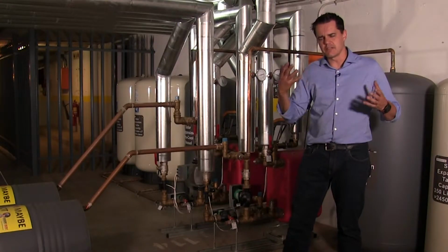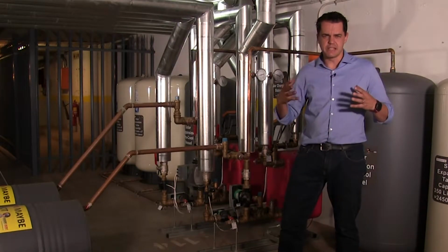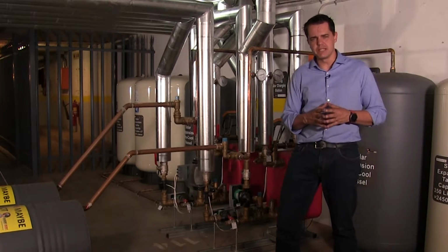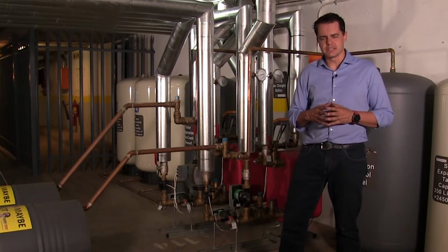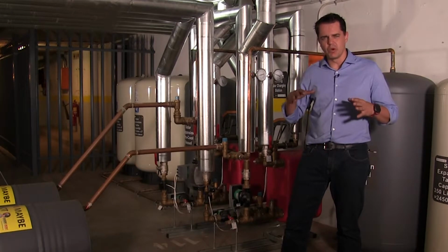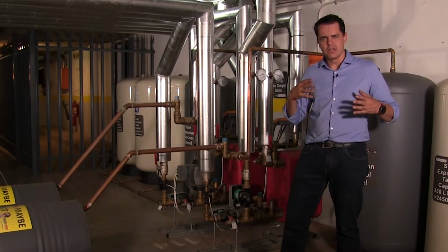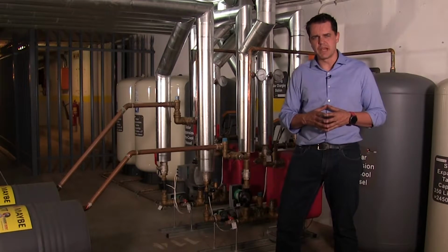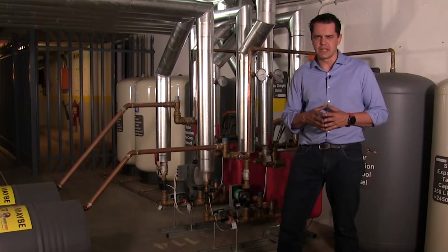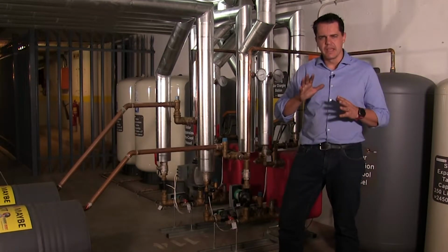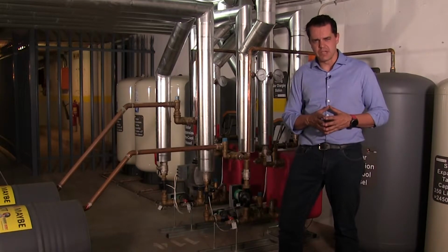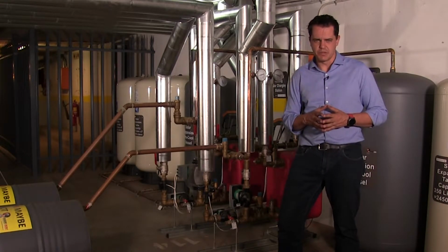This campus, as I've mentioned in previous videos, does have a full backup diesel generator setup, so there should never be a point where there's no electricity. So even if the Eskom supply is down and you can hear the generators running, but there's no power here, it means that somewhere the power has tripped and there's no power to the solar plant.